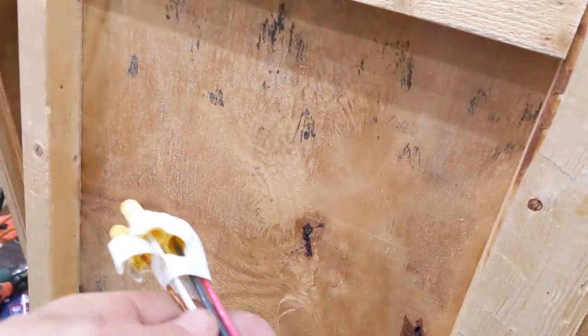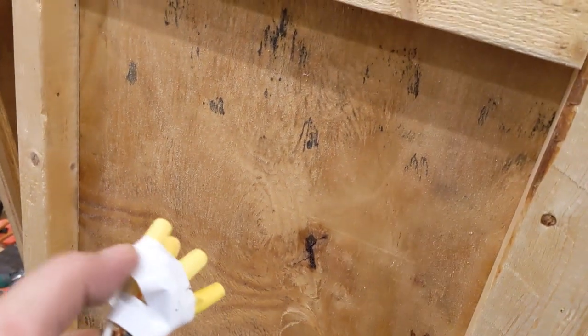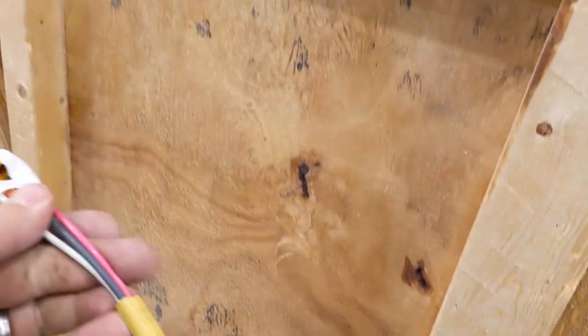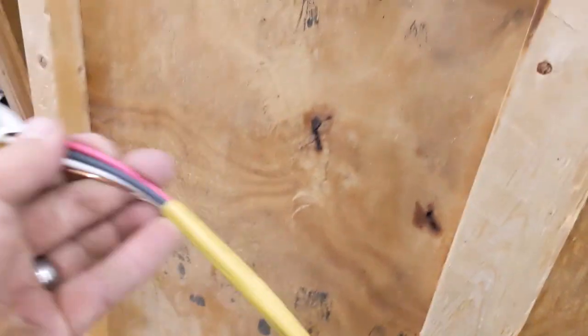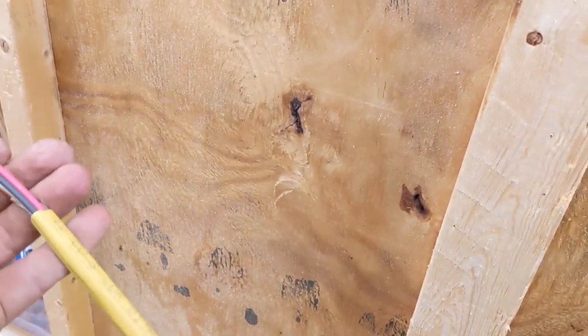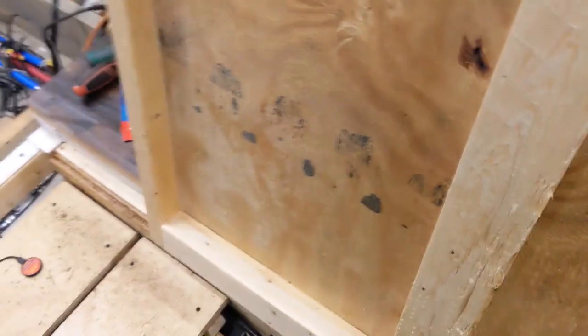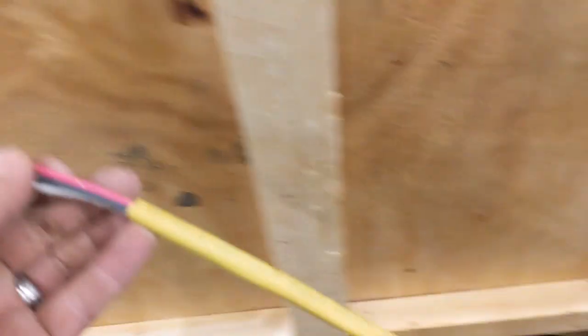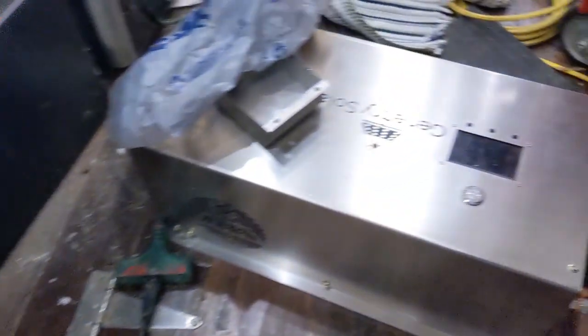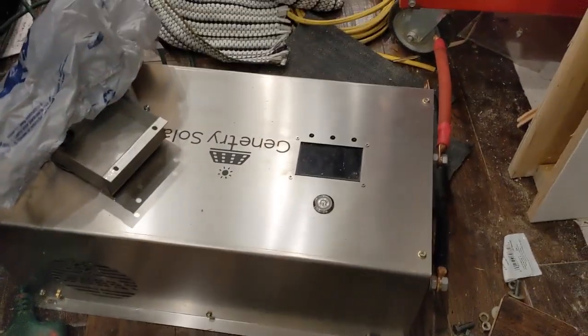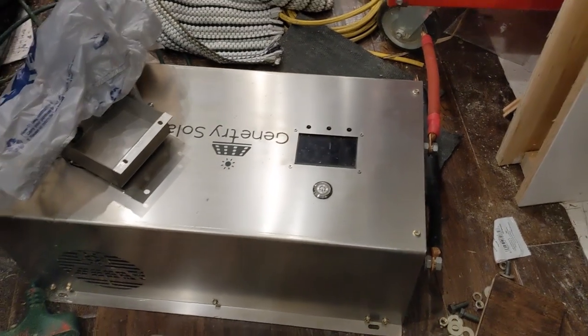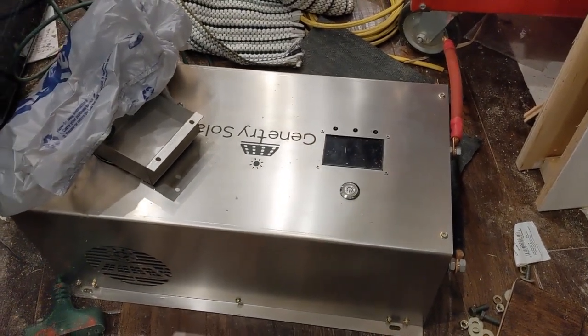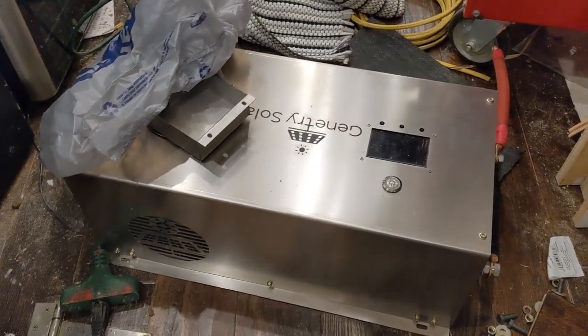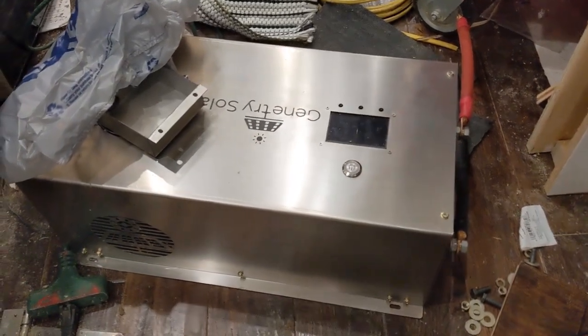And what I'm going to do is cover this in electrical tape with these wire nuts, roll it up and make sure it's not going to short against anything. So I'll label it as well. But we're going to put the AC into the inverter at 20 amps, 120 volts, because the max throughput for charging is only 25 amps anyway. And based on the size of the battery bank, it'll give a reasonable charge.